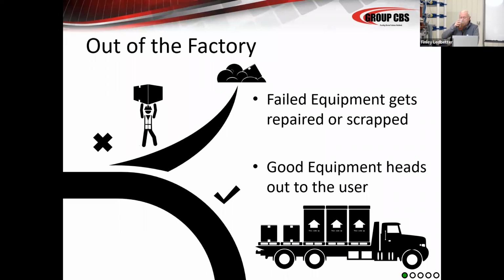When it comes out of the factory, obviously, if it fails these tests, some things are scrapped. There's a little scrap pile, and then sometimes a guy gets it and repairs it and it comes back. That's called a first pass testing. So sometimes some things that fail can't be repaired. Let's say a piece of epoxy or composite insulation fails. Well, it's pulled out and scrapped. Let's say a vacuum interrupter has a high leak rate and it fails. There's all sorts of things that can fail in this testing process, and it's replaced with a new component, okay? Because their first time pass rate's not 100%, nor is any type of switchgear, any type of manufacturing.